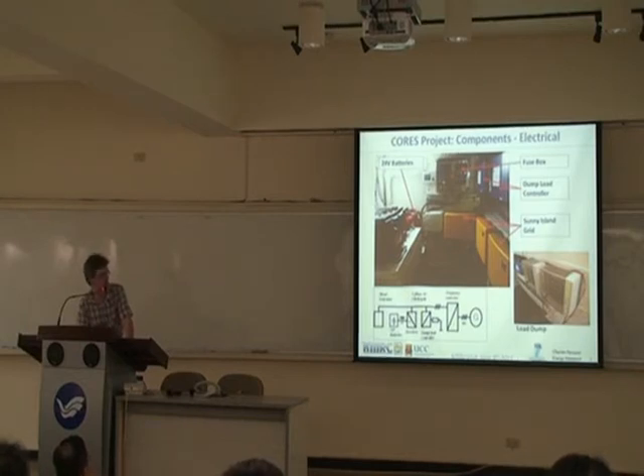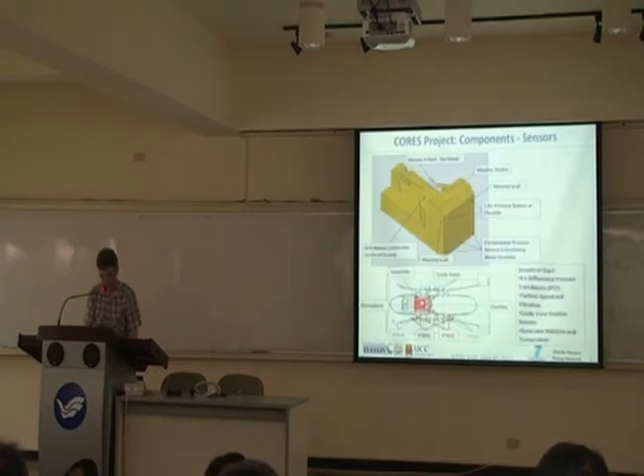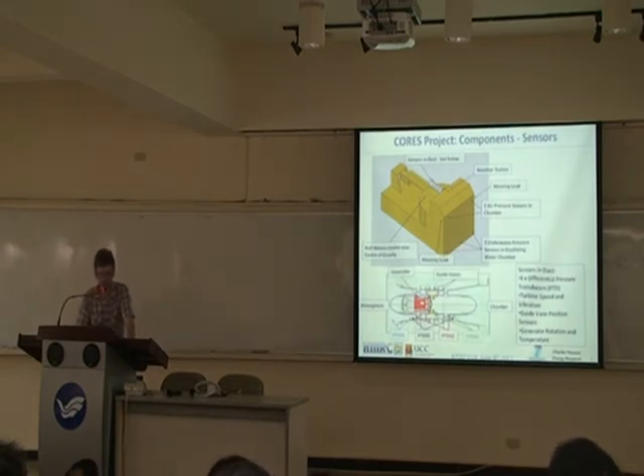So when the system is generating power then, the power flow comes from the generator, primarily charges the batteries. If the batteries are fully charged, there's a dump load controller which changes the frequency of the grid, and in so doing controls the amount of loading resistance that's connected to the system. Gets rid of the excess power. Just looking at some of the sensors on board, we try to put as many sensors as possible into the system so that we can understand and get good research data.